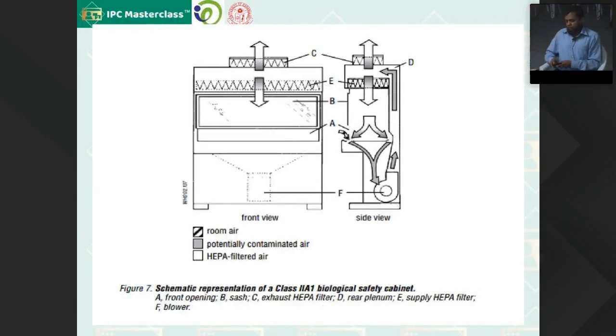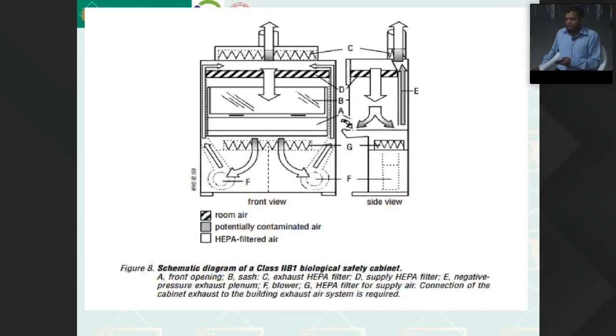So this is the class 2 biosafety cabinet where you have the entry of air through this, and here you have a grill. From there it goes through the plenum, it goes up. Here you have an exhaust HEPA filter, and here you have the working HEPA filter from where air falls into the workstation. And this is how the direction of air goes. It comes from here and goes through the plenum. Here, 30% will get exhausted, 70% will get recirculated, and it passes through these HEPA filters and falls onto the workstation. But it will not allow the person who is working or sitting here to get cross-contaminated or infected with this air.